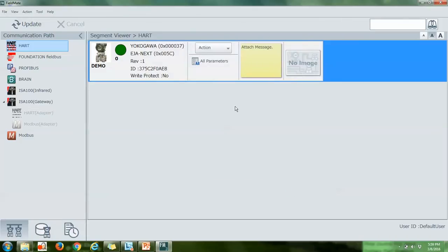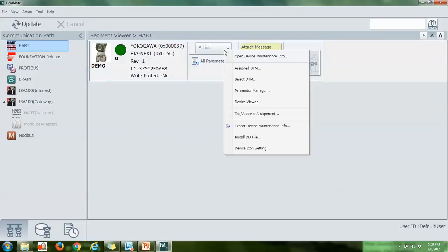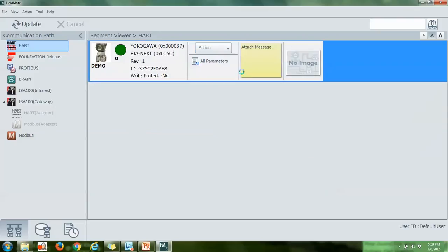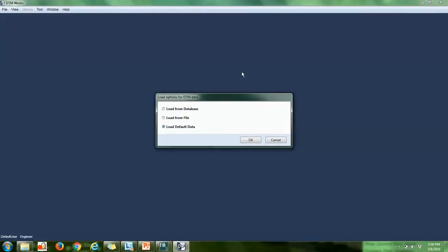So again, we want to go in. In this example, we've got a transmitter that's out of tolerance. So we're going to go to Action and Assign DTM. With this Yokogawa device, it should automatically assign the correct DTM and pull it up for this specific EJA.